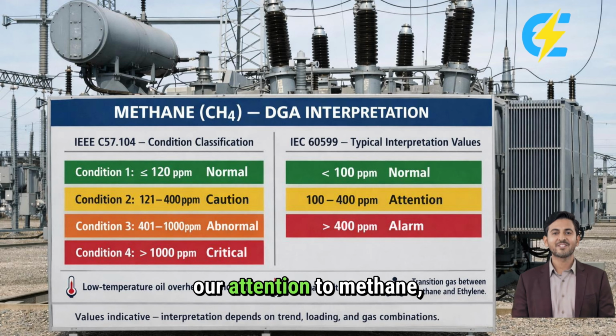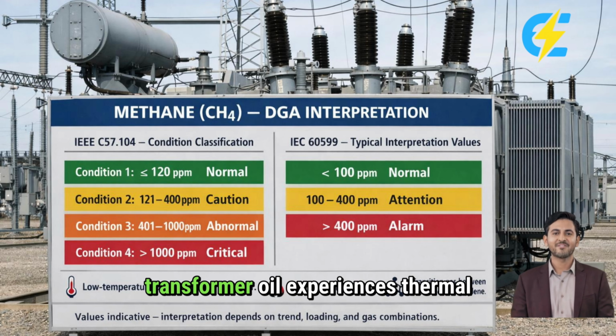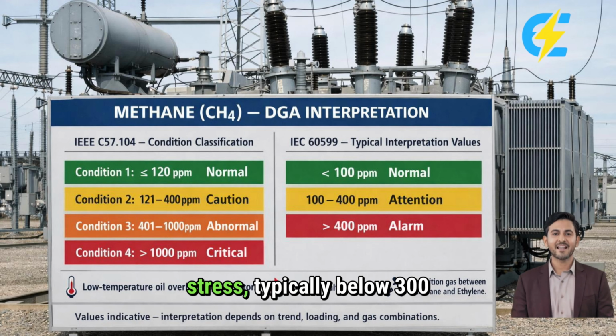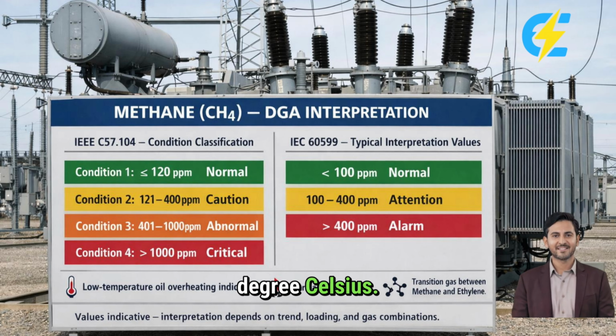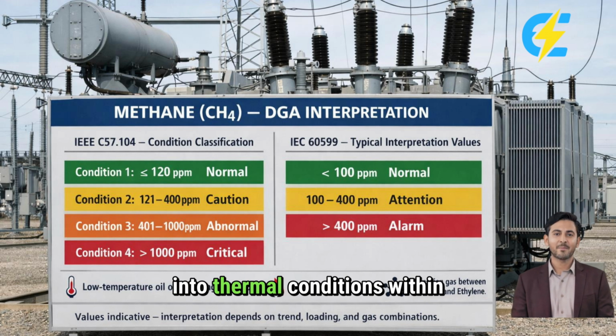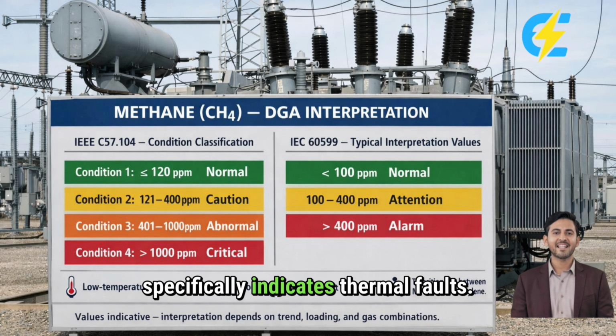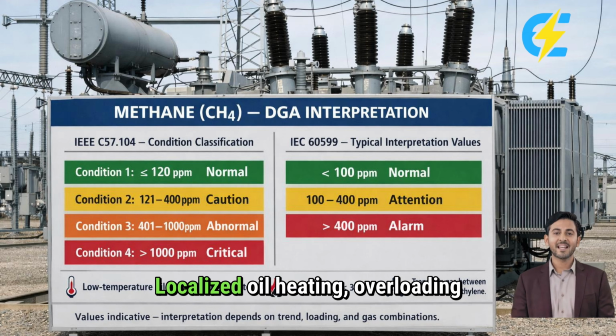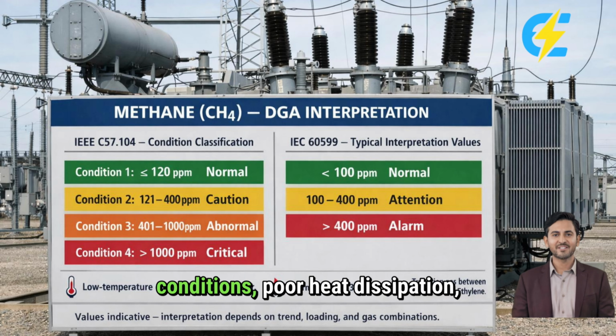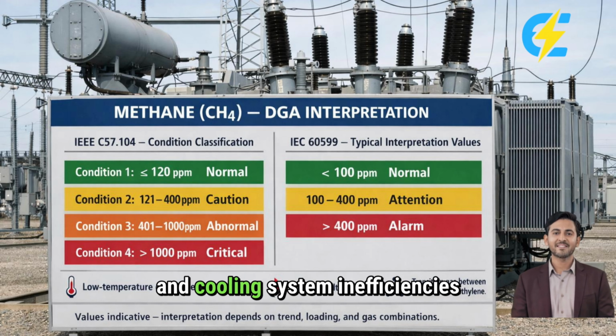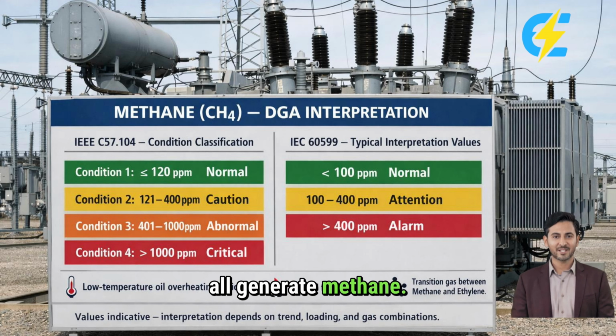Now let us turn our attention to methane, the thermal fault indicator. Methane tells you that heat is present but not extreme yet. This gas forms when transformer oil experiences thermal stress, typically below 300 degrees Celsius. Methane is your window into thermal conditions within the transformer. Unlike hydrogen, which responds to electrical stress, methane specifically indicates thermal faults. Localized oil heating, overloading conditions, poor heat dissipation, and cooling system inefficiencies all generate methane.